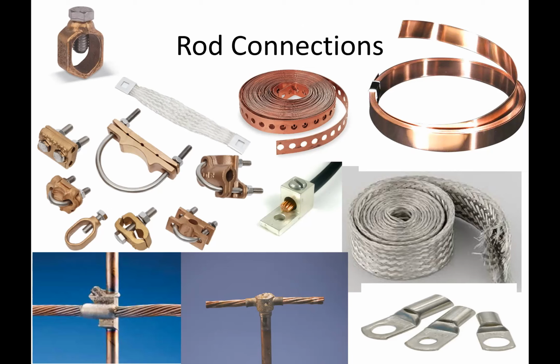KC1DOY: I just wanted to point out the rod connector, like the one you see in the upper left hand, that screws on over the rod. If you're like me and use the brute force hammered-into-the-ground method of putting in your ground rod, put that connector on the rod first, because you may flatten out the top of the rod as you're hammering it, and then it won't want to slip down easily anymore. So although you can file it down later, it's easier to put it on first and then put the rod in the ground.